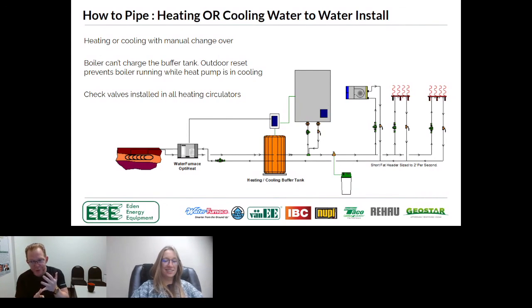Yeah. So the reality is your heat pump will do that too. It'll make weird noises. We talked about that. If you burn it up, you'll smell it. I was at a heat pump where they were running it at 150 degrees for probably a month before somebody called me and said, something's not right. And I could smell burning plastic when I walked in. Now you might ask, but there's no plastic on the compressor. I'm like, no, but it's the terminal connections to it all burnt off. So it was in the process of killing itself. Unfortunately, I was right. The units did die about a week later, and I'm not happy about it.